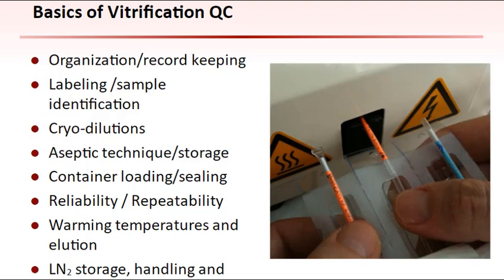The basic quality control factors needed to make vitrification a consistent, efficient, reliable, and effective ART procedure include the following. Organization: having paperwork or computer records as well as vitrification setup fully prepared prior to initiating vitrification. Labeling: ease, accuracy, and reliability of sample labeling and identification are of critical importance. An ideal system includes a dual color system with duplicate labels or a tamper-proof label system. Cryodilutions: distinct dilution steps so that solution purity is maintained and precisely timed without variation.